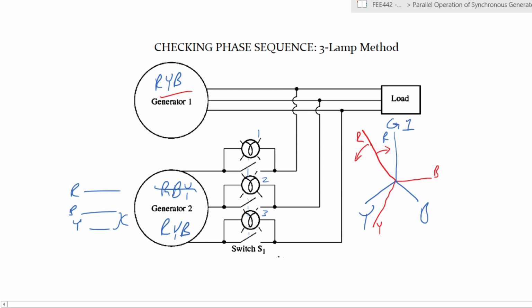So if it is faster, it is moving away, say in an anti-clockwise direction. If it is slower, it is moving towards it, say in a clockwise direction. And it is that difference, because if you look at this circuit, this is the equivalent of your red from the main circuit, and this is your red phase from the generator 2 circuit. So your lamp is connected across these two, right? And your lamp here is also connected across these two and across those two.